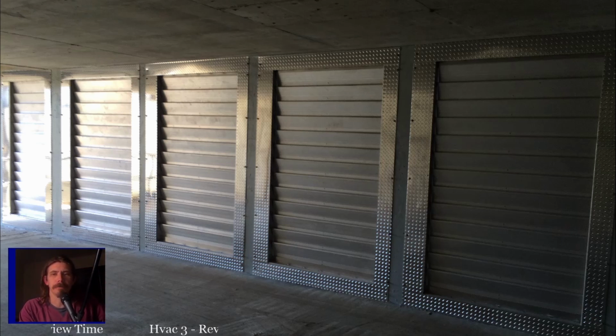Or it's just cycled too many times because something's wrong with the system. So that relay was cycling a lot, and that'll cause a relay to fail or a contactor to fail. And then the other thing that I see a lot, and it's something you should look out for, I don't see capacitors pop on boards that often, even though they can, really old circuit boards, usually the capacitor failing is what'll finally kill it.